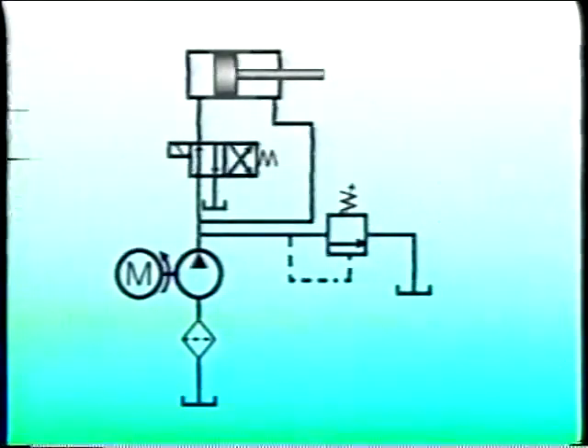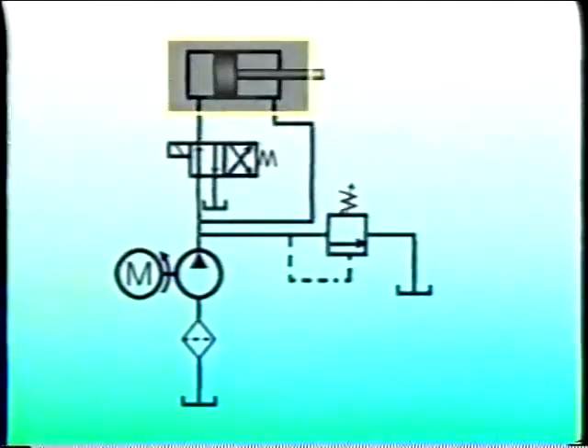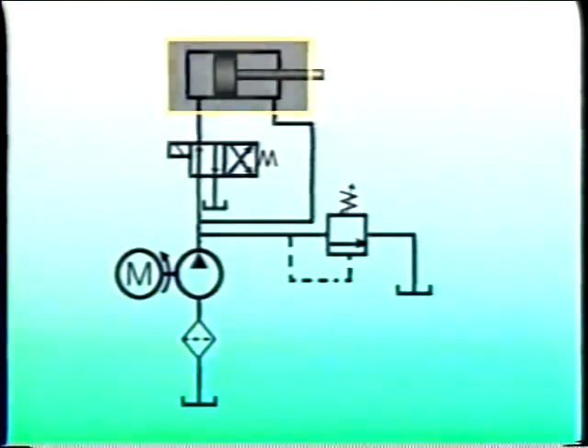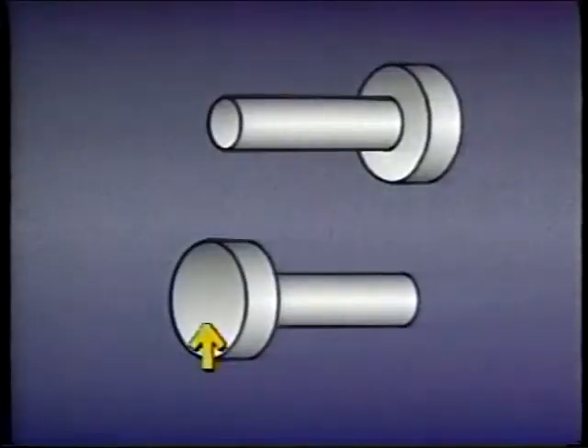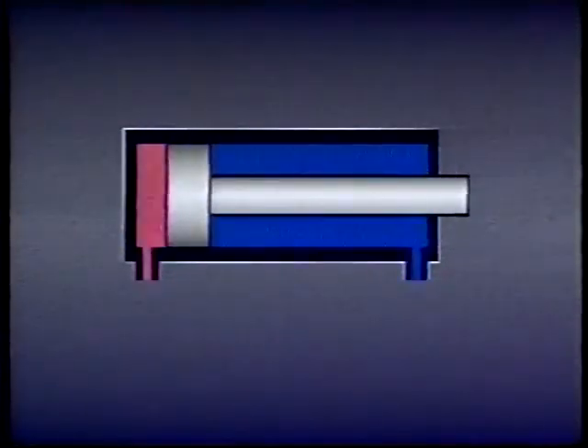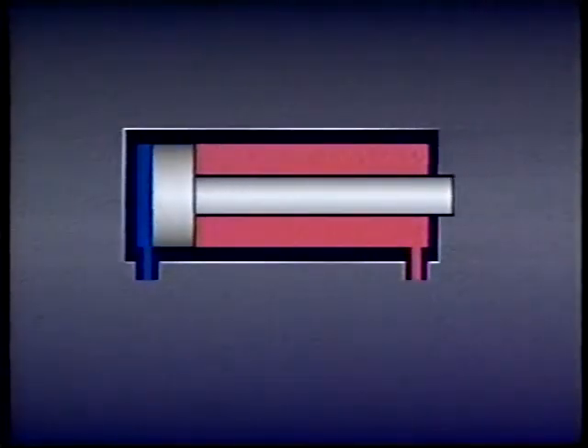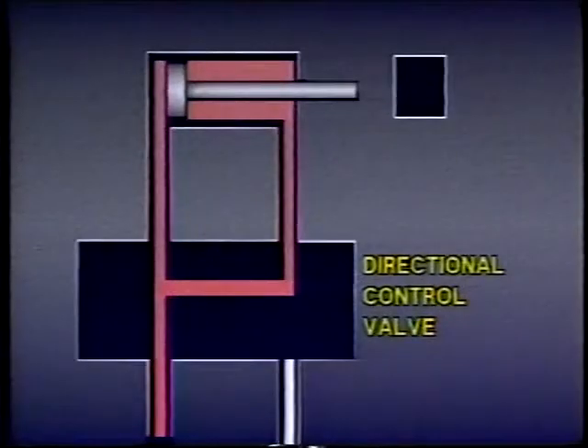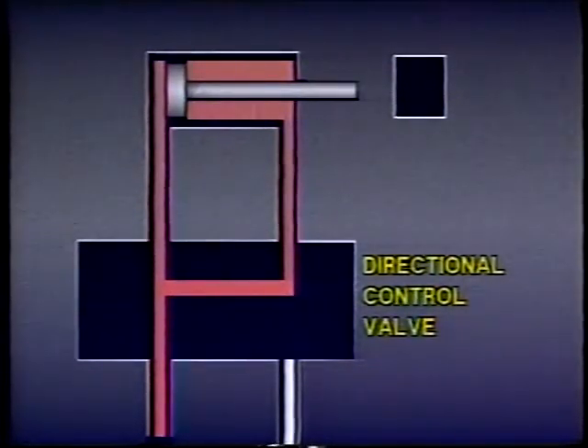Another way to match the velocity of rod extension and retraction is to use a two-to-one cylinder in a regenerative circuit. In a two-to-one cylinder, the area of the piston at the cap end is twice the area at the rod end. If flow on extension were equal to flow on retraction, the rod would extend slower than it retracted because there is more volume to be filled on the cap side. However, when used in a regenerative circuit, fluid from the rod end is discharged back into the cap end, increasing the total flow and equalizing the speed.